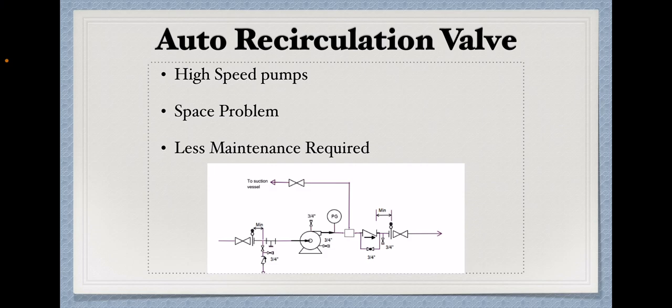So, as the forward flow drops, the pump discharge pressure increases and at a certain point, the spring in the auto recirculation valve will open to maintain the recirculation flow. So, this ARV is very reliable in nature and very less maintenance is required.